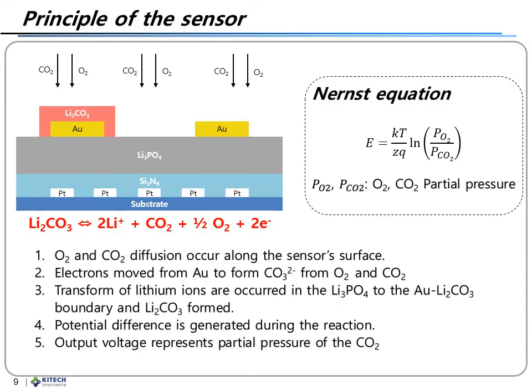This is the principle of the carbon dioxide sensor. First, oxygen and carbon dioxide diffusion occur along the sensor surface, and electrons move from the gold electrode to form carbonate ions from oxygen and carbon dioxide. Then, transport of the lithium ions occurs in the lithium phosphate to the gold-lithium carbonate boundary, and lithium carbonate is finally formed. The potential difference is generated following the Nernst equation during the reaction, so that the output voltage represents the partial pressure of carbon dioxide.